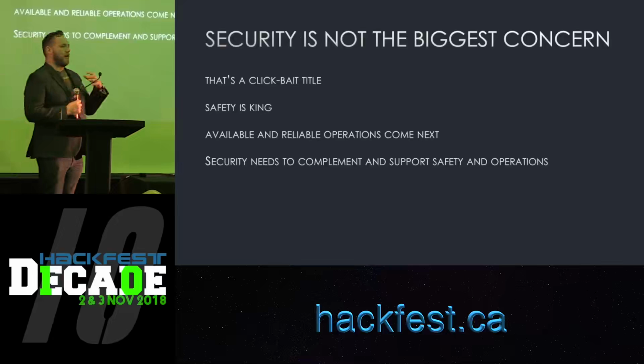So because you've got 500,000 devices, the only thing they're really doing from your point of view is talking to each other. So from a defense point of view, you need to understand what that communication pattern looks like, and who talks in which direction. If you've got a master and slave set of devices, then really I should only be sending writes down and reads up - that's the only thing I should see. So if a write is coming from an end device you weren't expecting it from, that's a red flag.